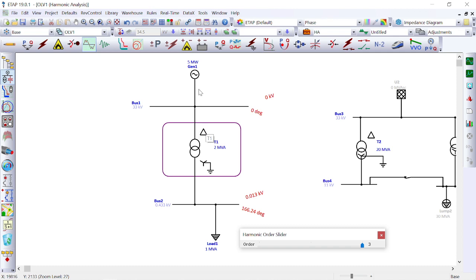So we understand from this simulation that if delta is taken on the inverter or generator side, the third harmonic current will not be transmitted to the generator or inverter — it will be protected. In every generating power plant, the generator side or inverter side selection should be delta winding. This is the first reason: protection against third harmonic current.